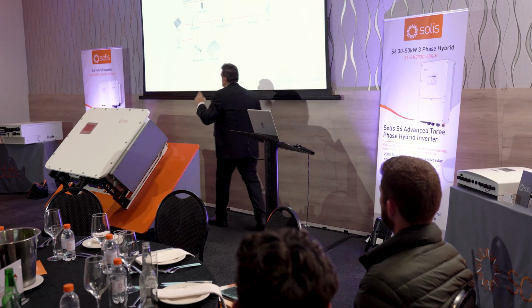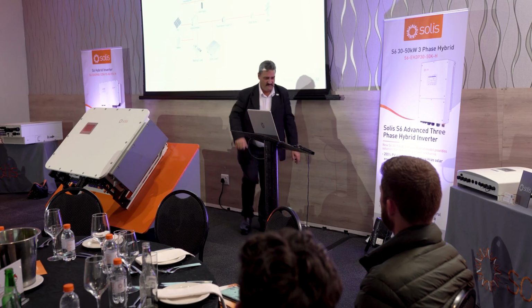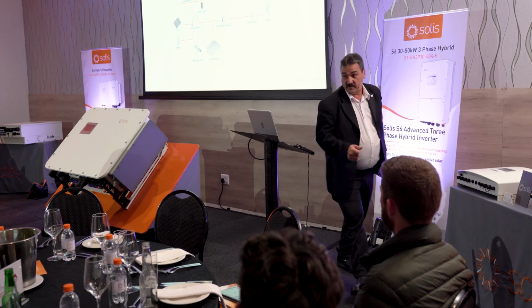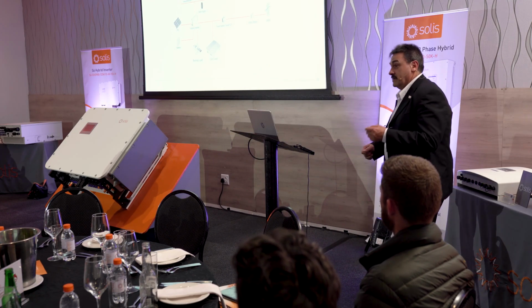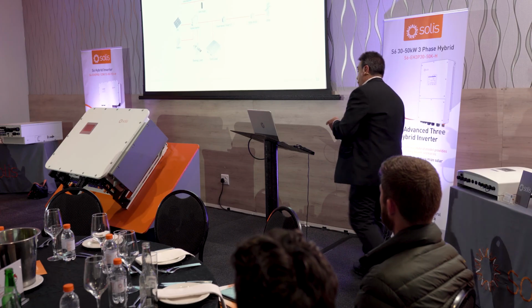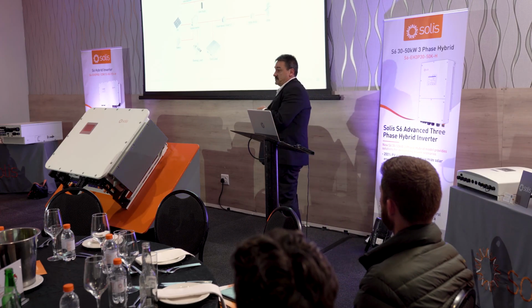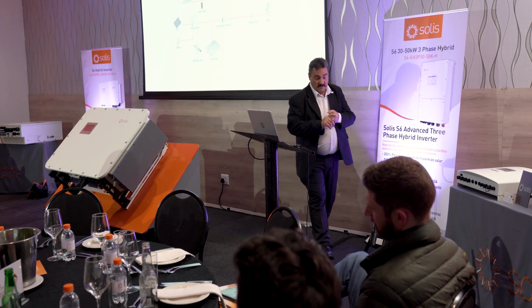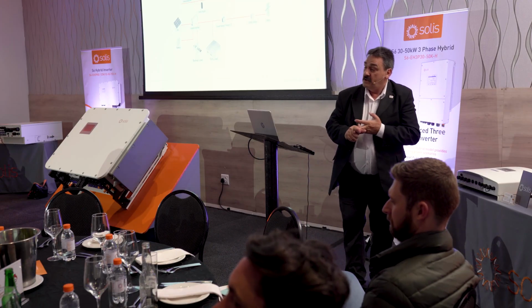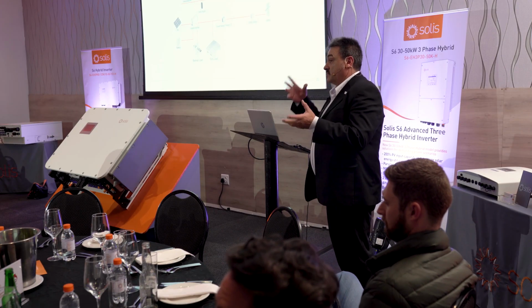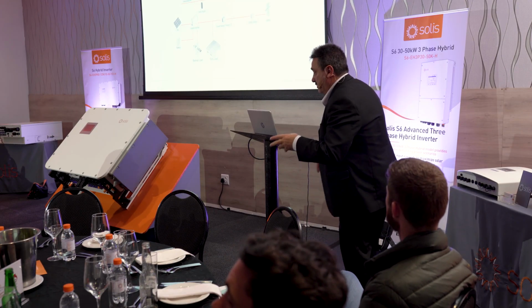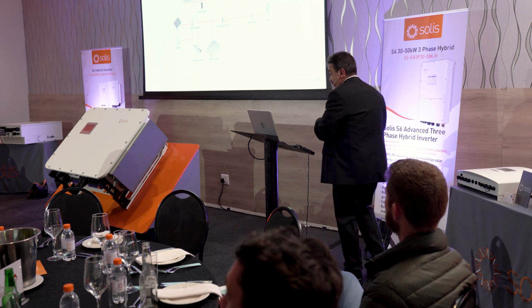But you can really use the system - you can set time of use functions. You have 12 settings for that, and 6 discharge functions, each of which can also be related to SOC, the state of charge of the battery. So you've got all these fantastic controlling bits and pieces of equipment that just aren't getting used.